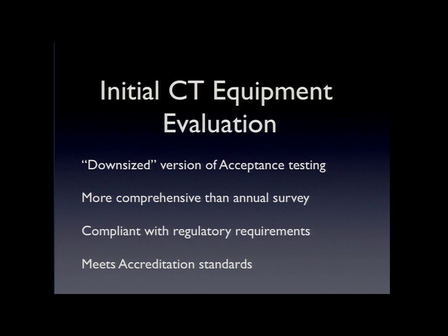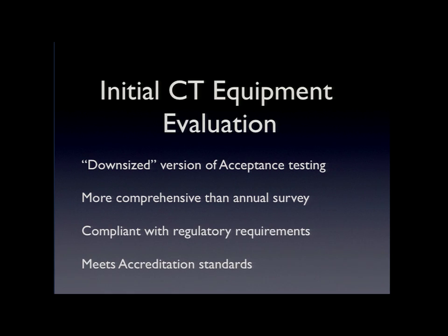It's more comprehensive than what you might do on an annual survey, but not quite as involved as a complete comprehensive acceptance testing would include. You want to make sure it's compliant with regulatory requirements. That's definitely one of the things you need to do before they start using it, hopefully. And then you want to confirm that it meets accreditation standards as well before they start using it.